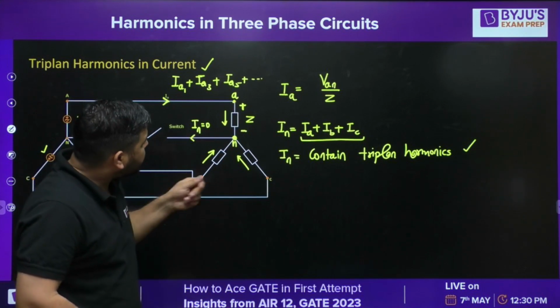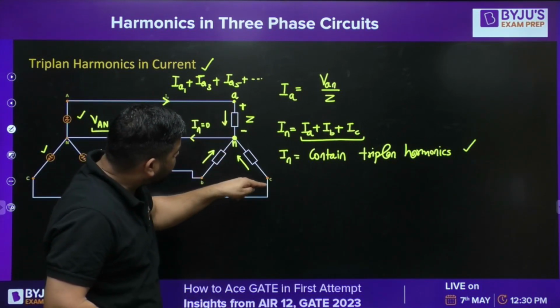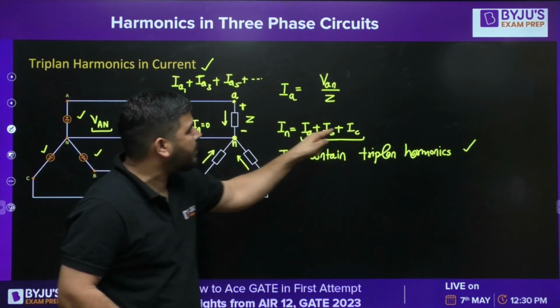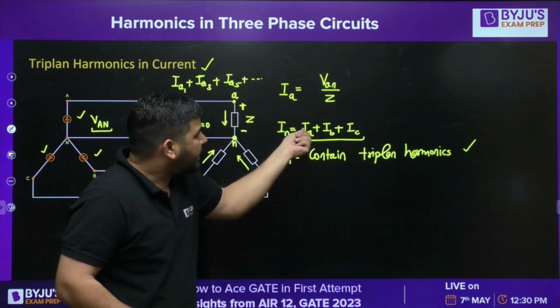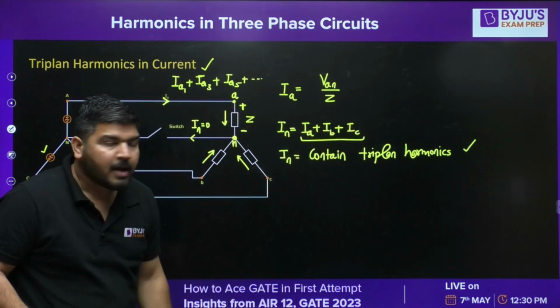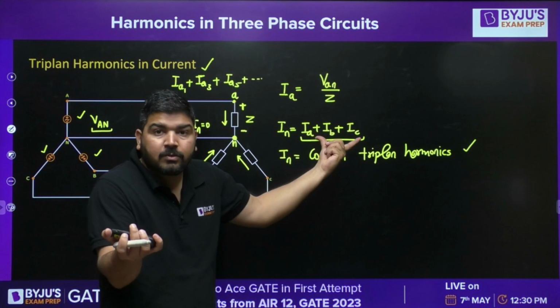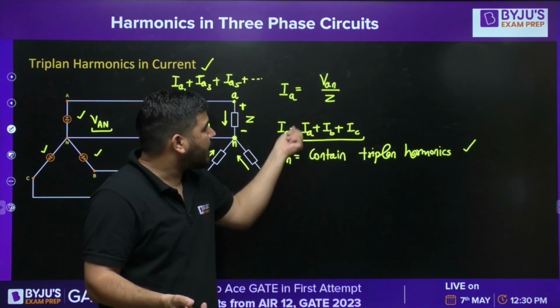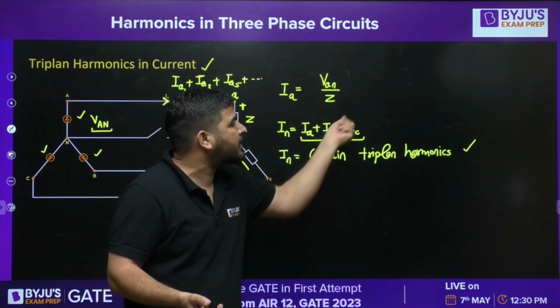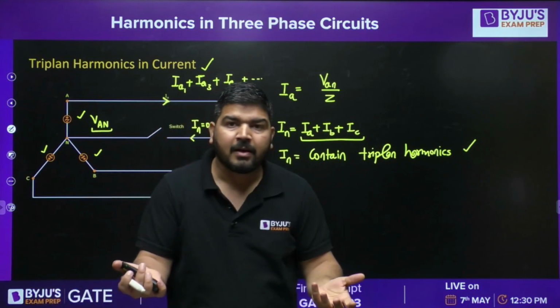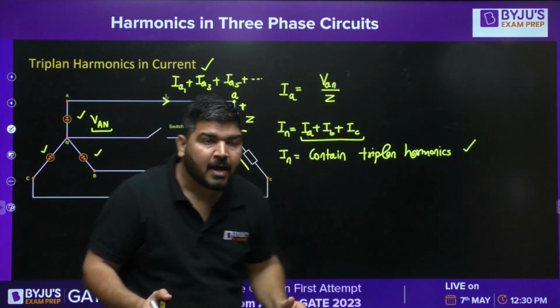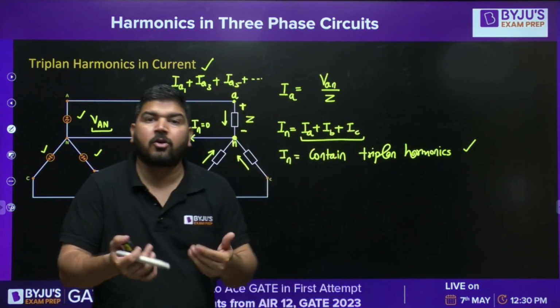Now you can see that if this phase current, IA, IB and IC, contain triplen harmonic, then their sum cannot be zero. Because the third harmonic in phase A, third harmonic in phase B and third harmonic in phase C must be in the same phase. And if they are added, they cannot be zero.